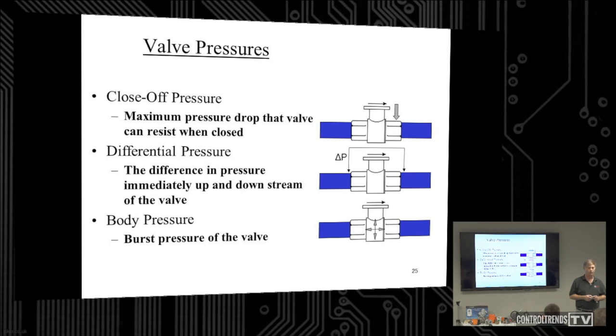First, let's talk about pressures. We have to understand if we put a valve in, maybe change out a valve, changing out old style to new style. We need to be concerned with close-off pressure, differential pressure, and body pressure.